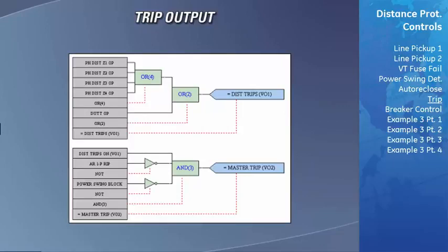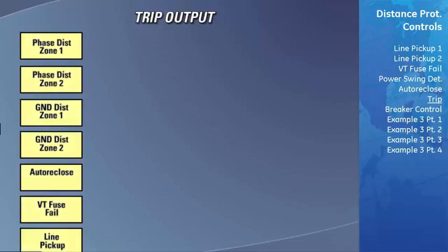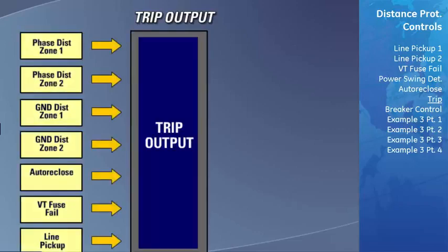This is known as the trip output logic. Using the trip output feature, the user now only needs to enable and configure all of the distance protection elements, pilot schemes, and control elements that they want to use. All of these elements are hardwired to the trip output through the D60 internal logic. The trip output feature takes into consideration all of the possible logic that might be needed for line distance applications, such as protection elements, pilot schemes, breaker fails, and so on. Using the pre-programmed logic, the trip output now determines, based on the status of all of these inputs, whether or not the breaker should be tripped or reclosed.